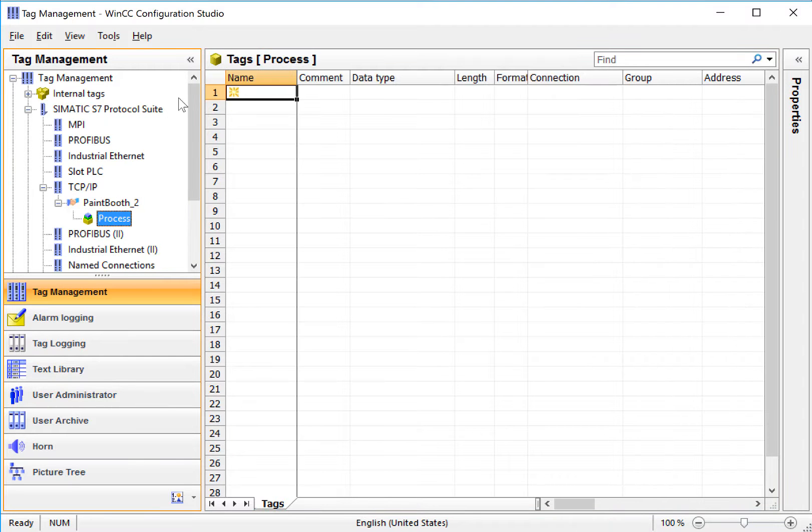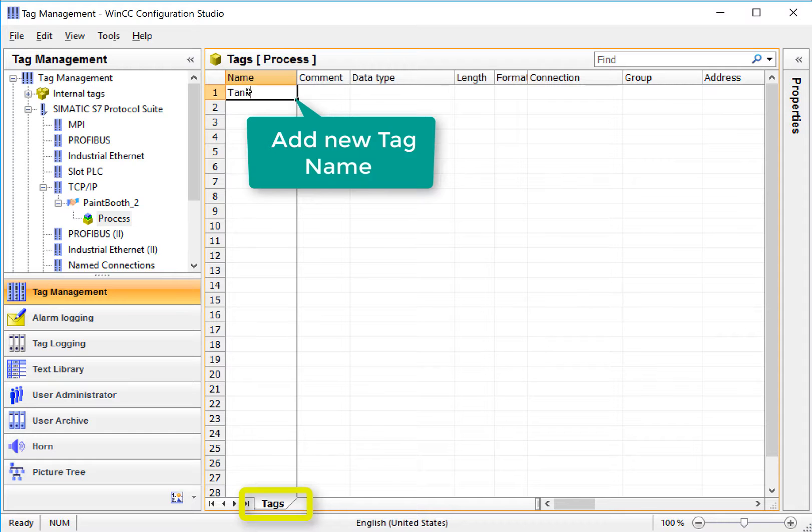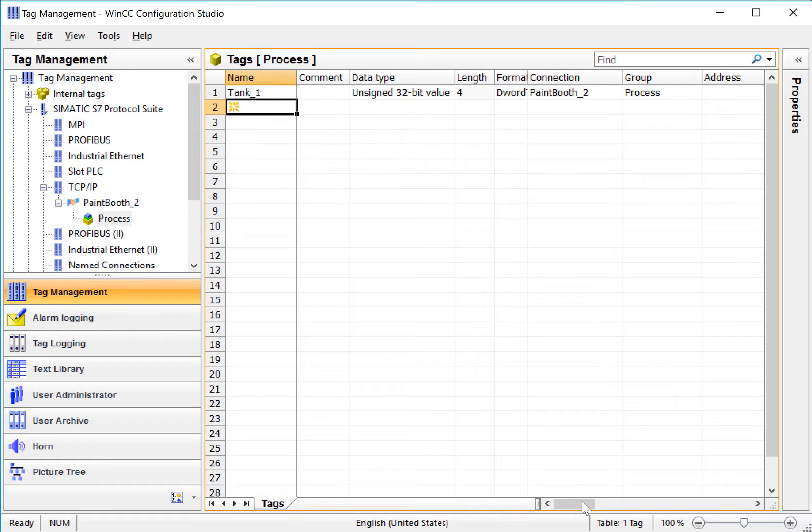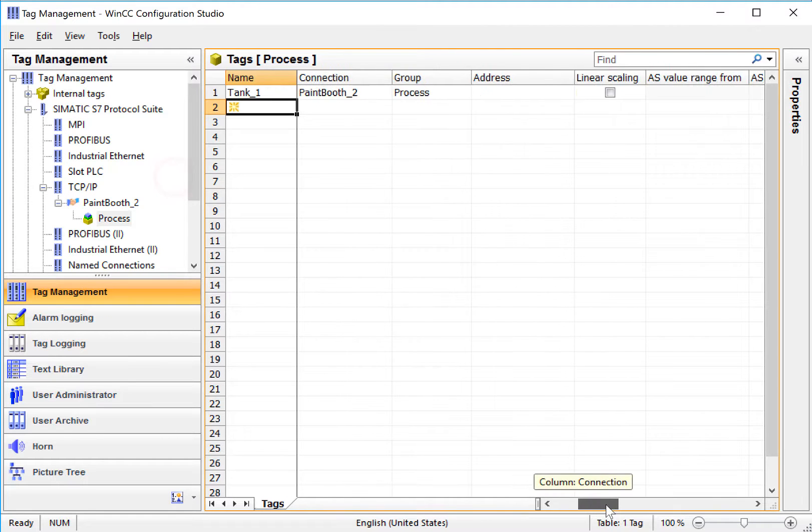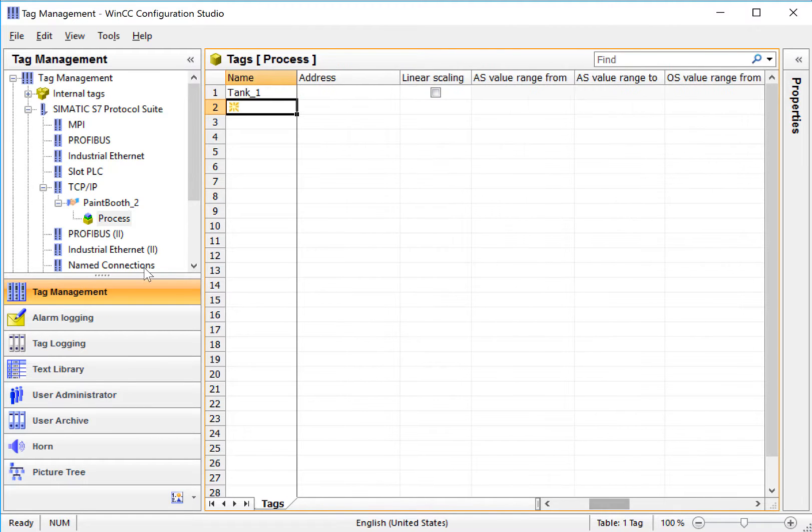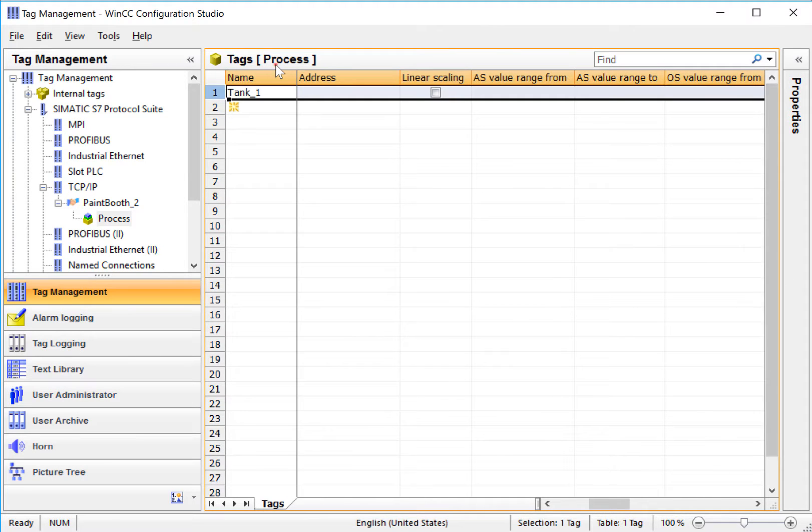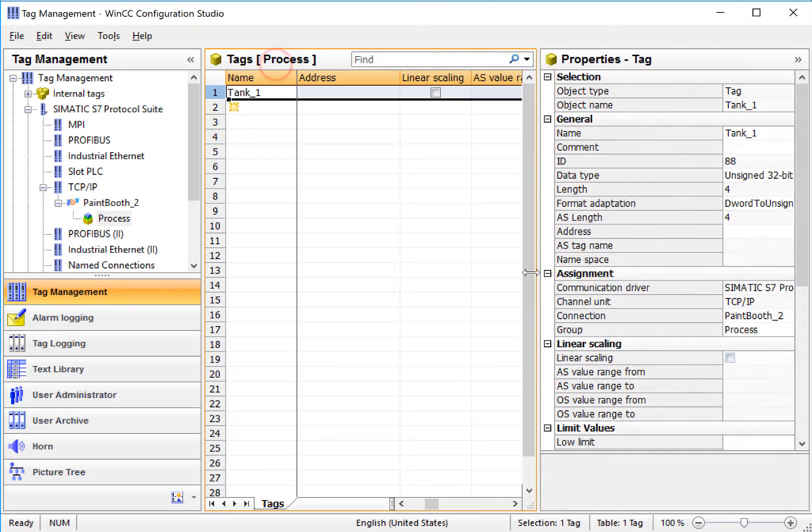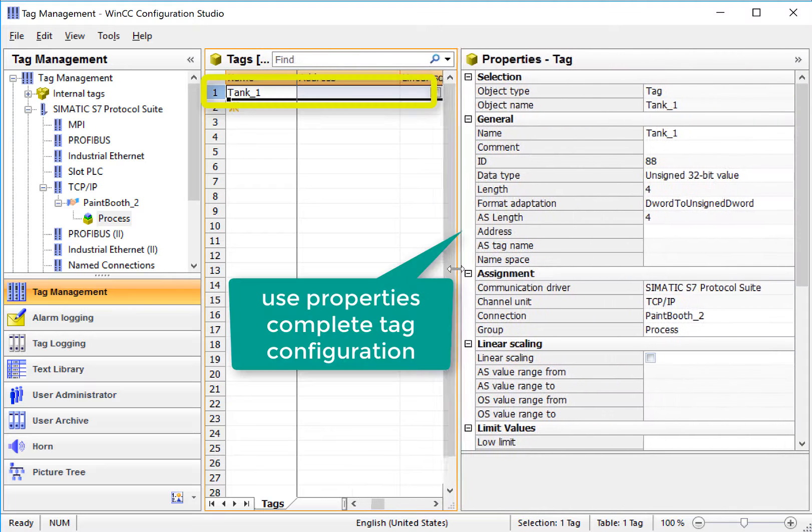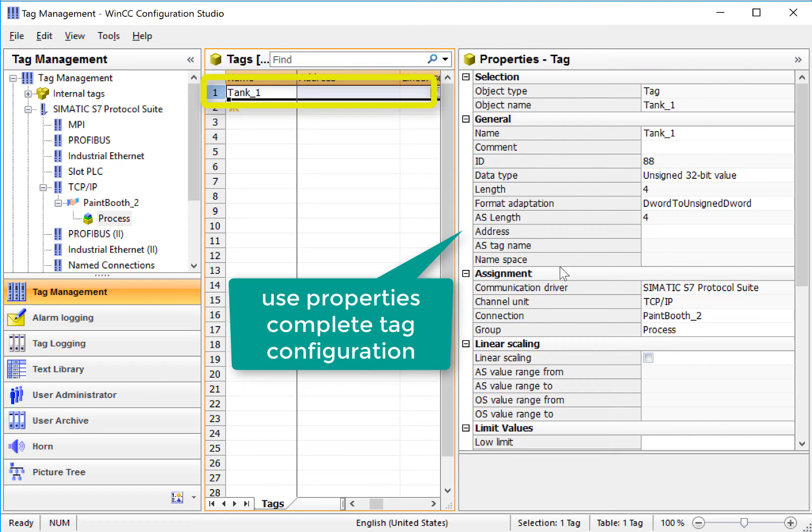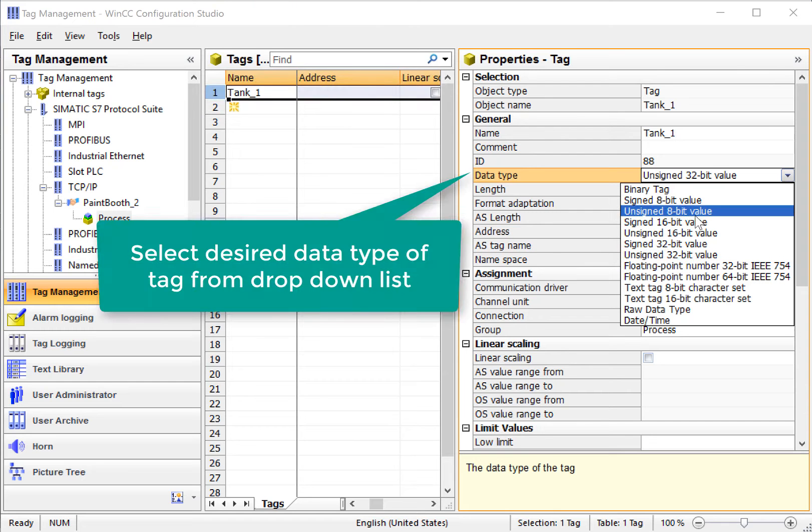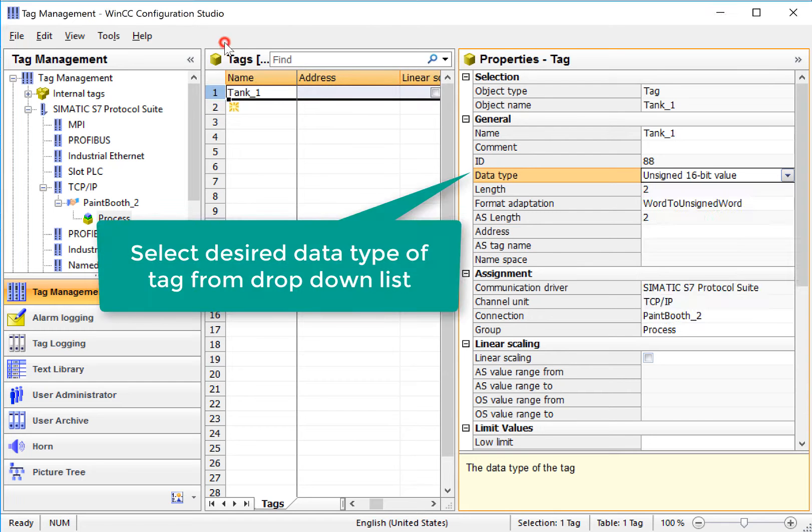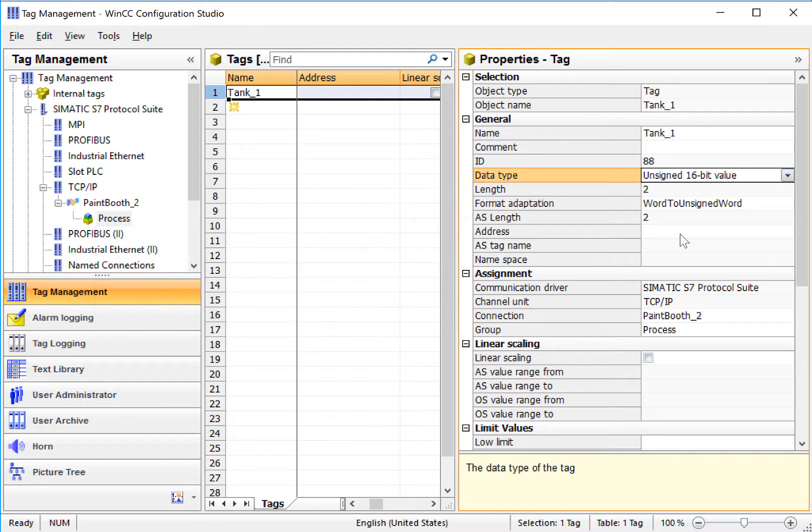So I can highlight process, and I can just start typing tag names. I'll create one called Tank1, and we can use the work area to configure this, or we can use the details area to allow us to assign the address. The first thing is the data type. For this, maybe I want to use something like an unsigned 16-bit value.